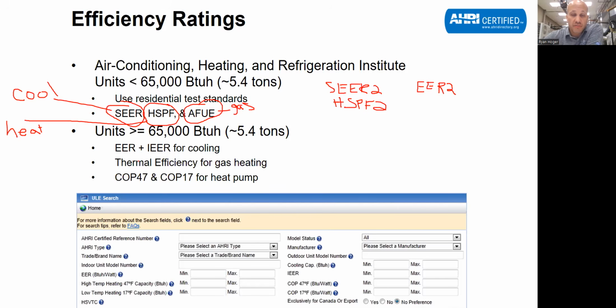Once you get to bigger stuff, 5 tons and larger, or 5.5 tons and larger, excuse me, then you don't get any of that terminology. There is no SEER or HSPF. We still have EER, which means run at maximum full. There's no EER2. We're still on regular EER there. Nothing's changed on their testing standard. And we have IEER, Integrated Energy Efficiency Ratio. That is a part load version. It's basically SEER for commercial stuff.